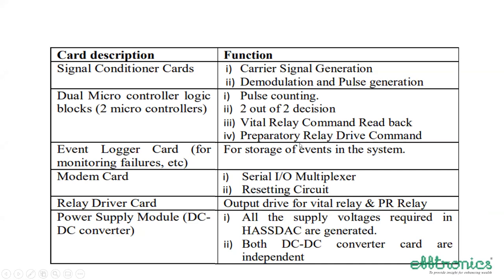Preparatory relay, we will cover it a little later. I'll tell you what it is. As I was telling, electronic systems are complex. We cannot just simply measure the voltages, currents here and there and declare it is faulty. So the events that are occurring inside this system are all logged by the event logger card, that is, the internal data logger.